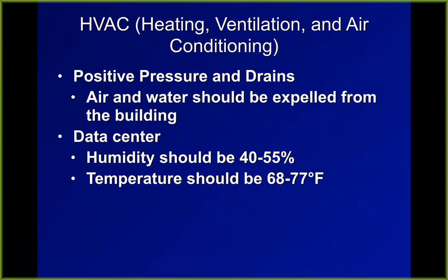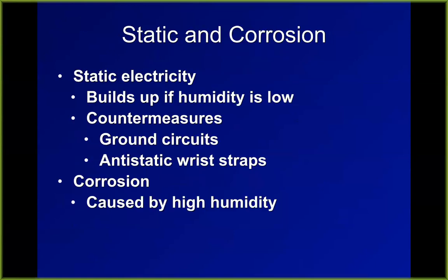Heating, ventilation, and air conditioning is important, of course. You want to have positive pressure in the building so that dust is being blown out of the building instead of being sucked in. Your data center should have humidity around 50% and temperature around 68 to 77 degrees. If the humidity is lower than that, you have static charge as people walk around and they're shocking things and breaking equipment. If you have higher than that, then water condenses on the devices and causes corrosion of the contacts.